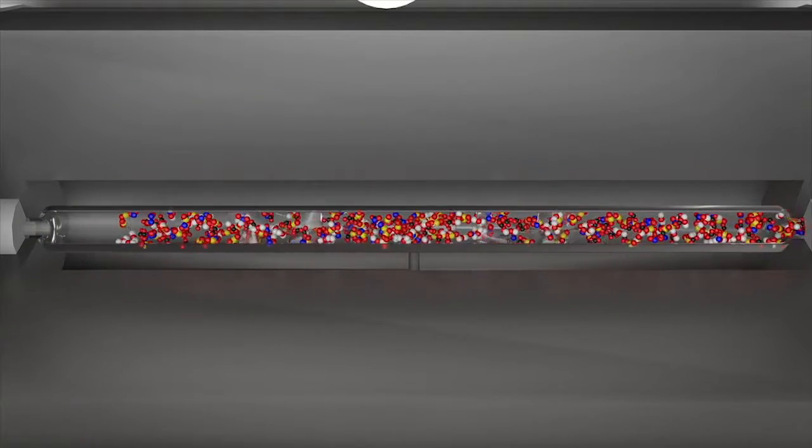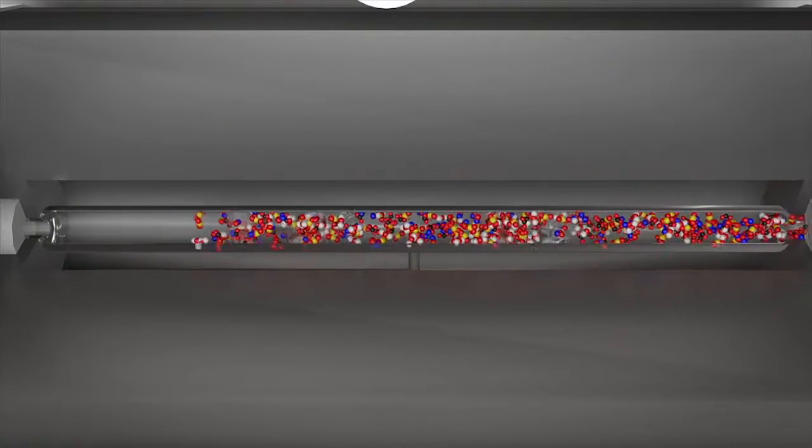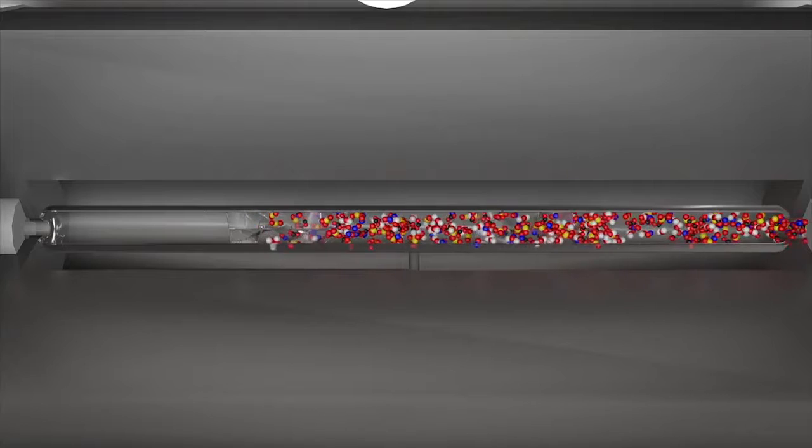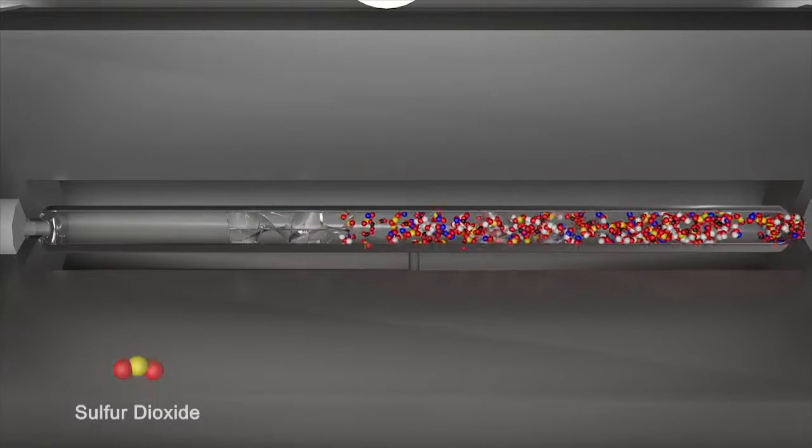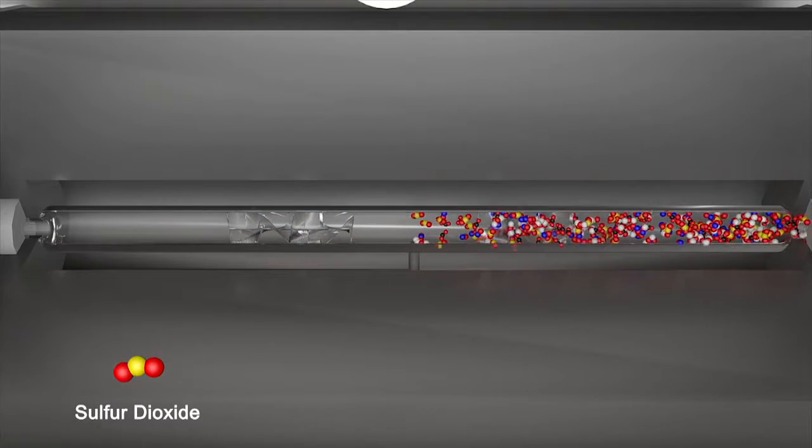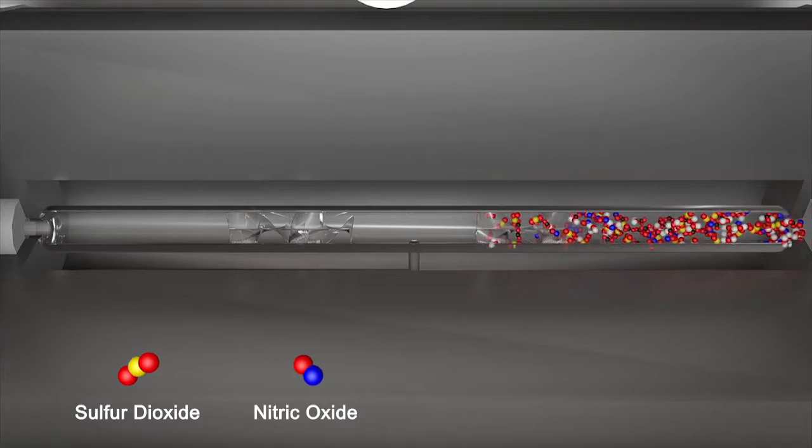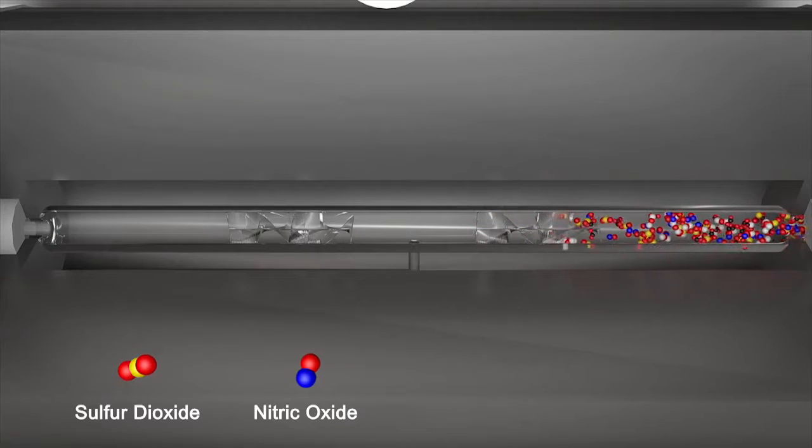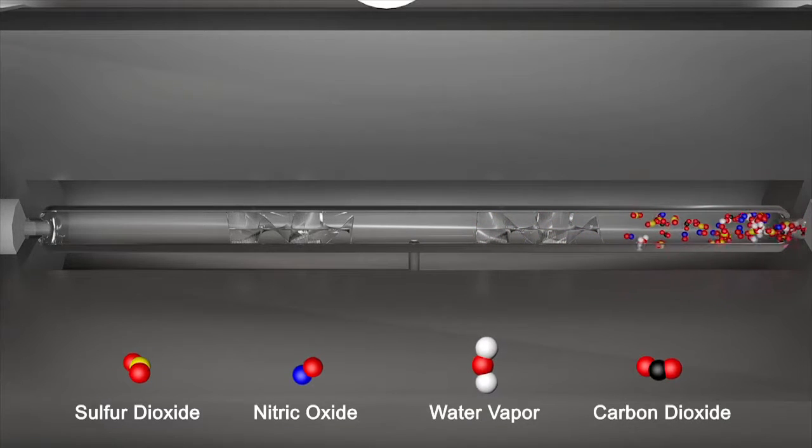Once in the furnace, the sample is completely combusted at 1050 degrees Celsius. This converts all sulfur species to sulfur dioxide and nitrogen to nitric oxide. The hydrocarbons are converted to water vapor and carbon dioxide.